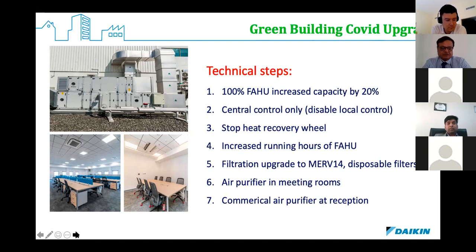The heat recovery wheel, when the weather was not good, was stopped so we could avoid mixing of air from the exhaust and supply side—though we have started it again now. The fresh air handling unit is running more hours, 24 hours now. Filtration was upgraded to MERV 14 and disposable type. In small meeting rooms, air purifiers were installed as an additional precaution, and big movable air purifiers were installed in large public and open areas.